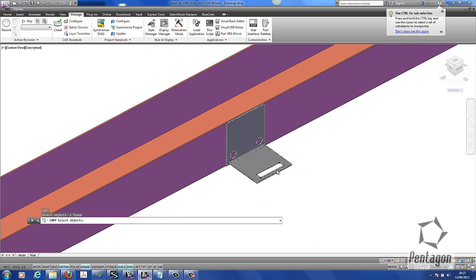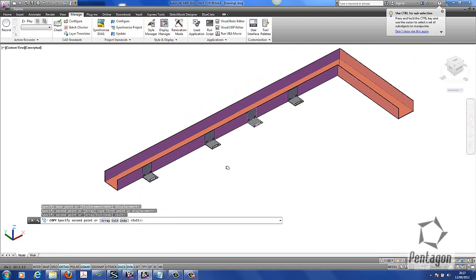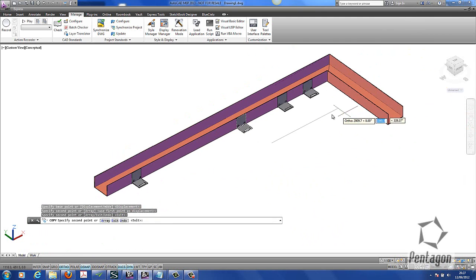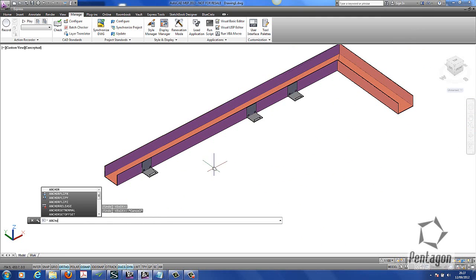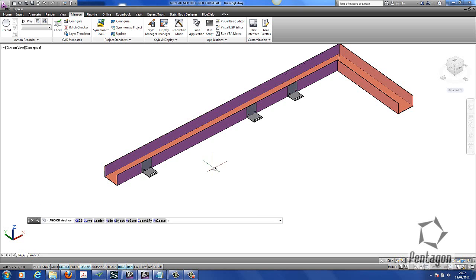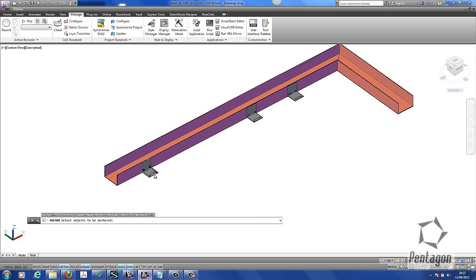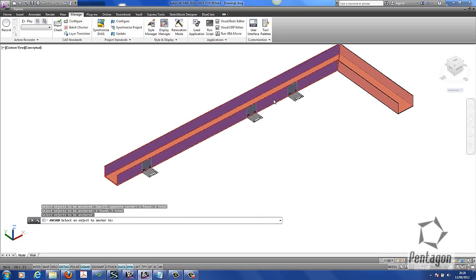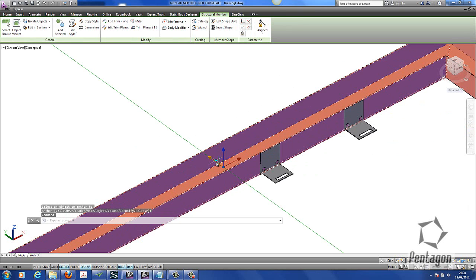I'm going to copy a couple of instances across. The advantage of using this method is we can use the anchor tool. The anchor tool is available in AutoCAD MEP and AutoCAD Architecture. I type anchor in the command line and we can anchor by object. We select the objects to be anchored — in this case our three brackets — hit Enter, then select the object it needs to be anchored to, i.e. the structural member, and hit Enter.